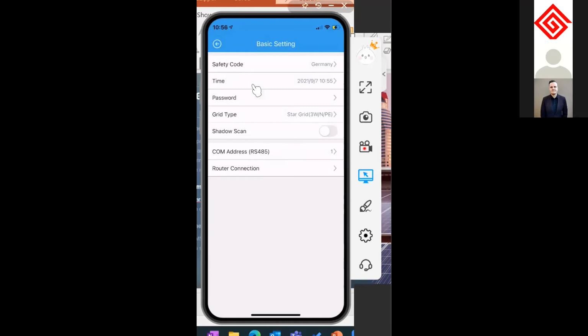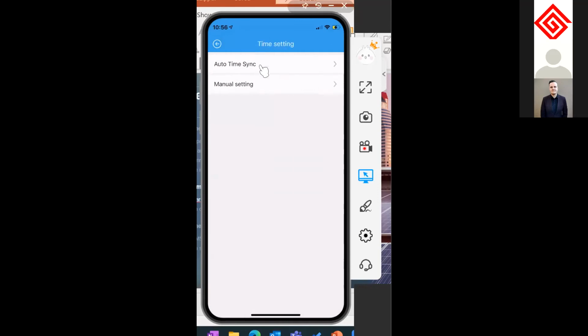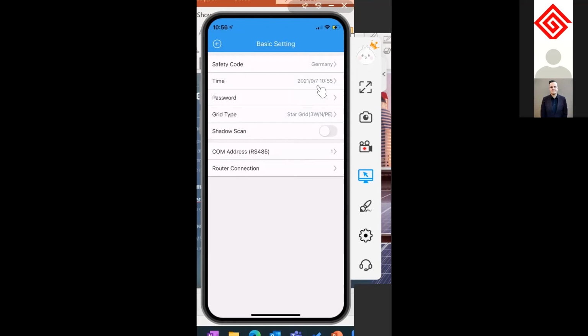After that, we click here on time. There are then auto time sync or manual settings. You can try auto time first. If that doesn't work, then please choose manual settings. Sometimes it's already recognized time on the inverter. In this case, it's already correct. So 2021, September 7th at 5 to 11.